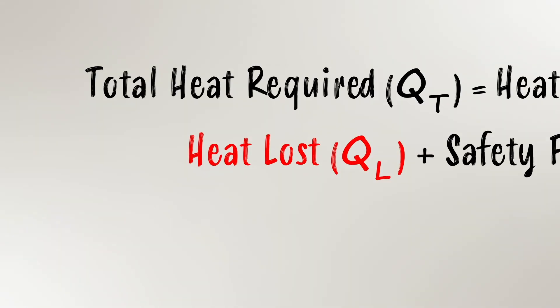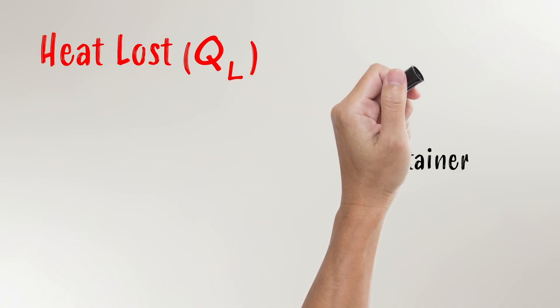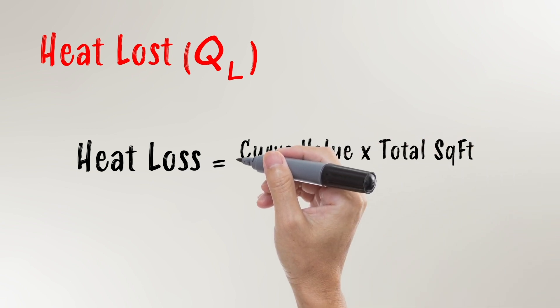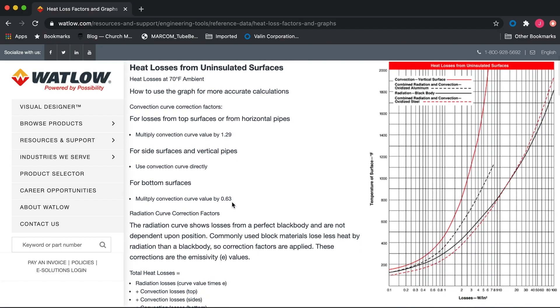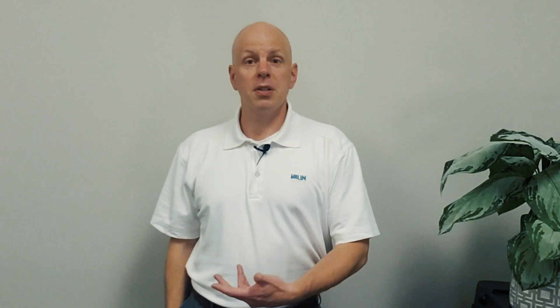Heat loss can have a significant impact when determining the kilowatts required. To find the heat loss, you need the area of the heated container, the materials of construction of that container, and the difference to the ambient. Heat loss curves allow you to determine the loss in watts per square foot per hour. After you know that value, plug in your values into the following equation: Q sub L, or heat loss, equals the curve value times the total square footage divided by 3412. This gives you the total kilowatts lost per hour due to heat loss. You can look up these curves online or plug the parameters into a computer program — the application engineering team at Valen runs these types of calculations all the time, so please contact us using the contact information in the video description.